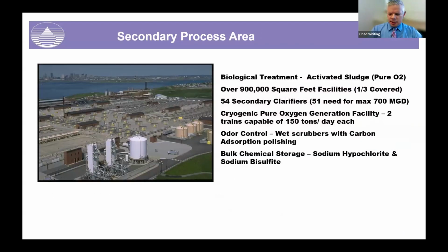This is an overview of the secondary process, over 900,000 square feet of area covered by our secondary process. In the foreground, you can see 2 white rectangular columns. Each one of those is a train for our cryogenic oxygen facility, where we generate our pure oxygen. In the process, we take ambient outside air and we compress it, we chill it, we purify it, and we rapidly expand it in those rectangular columns. And it reduces the temperature to minus 285 degrees. So the air is separated into gaseous oxygen and nitrogen. The gaseous oxygen is then fed to the secondary process for respiration to do the aerobic biological treatment of the wastewater, to remove any of the organic contaminants left over from primary treatment before it goes to disinfection.